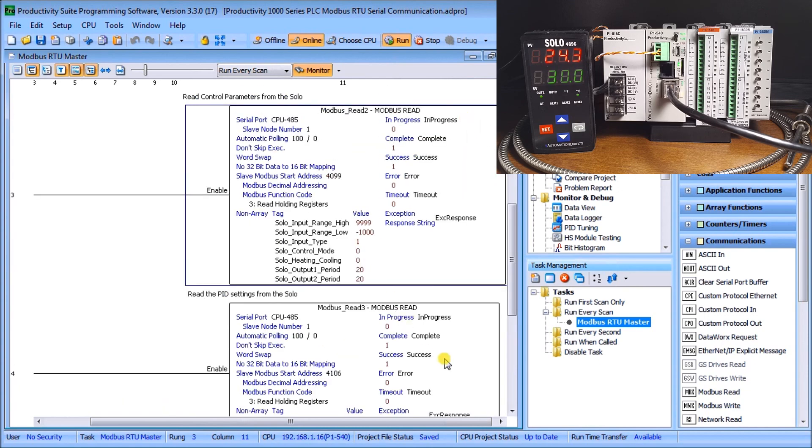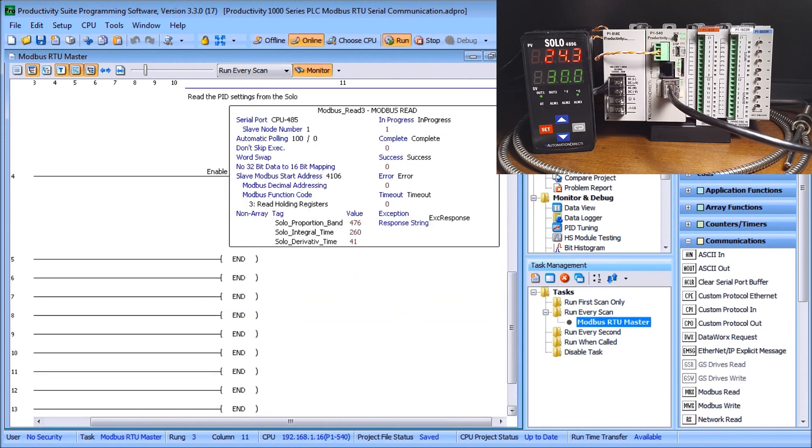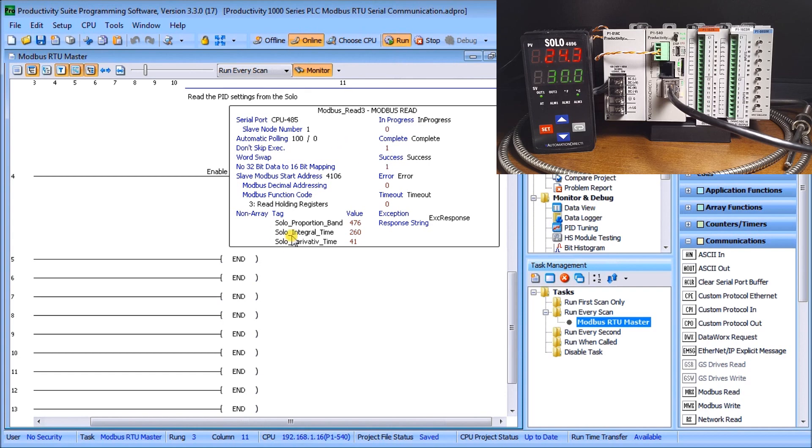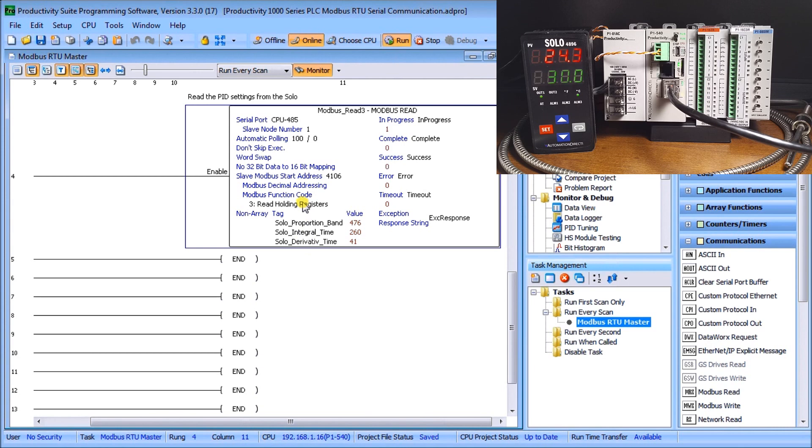Our last rung here we have another modbus, we call this modbus read three, and we're setting up and reading the PID parameters. So the proportional band, the integral time and the derivative time we're reading in from the solo into the productivity 1000.